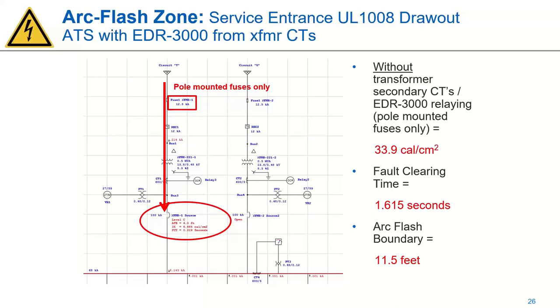You can imagine that I had that graphic up showing the different levels of PPE. That level 3 or level 4 moon suit does have some means of protection, the fire resistance. But you can imagine you're much more prone to making errors in something like that as well. You're going to have these big gloves and all these other things that are going to make it pretty difficult for you to do your job and maybe more prone to make errors. So this customer really desired the lower range, below the level 2, below that 8 calorie level.